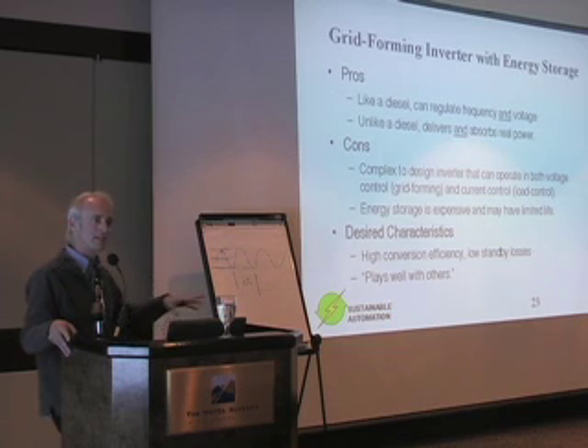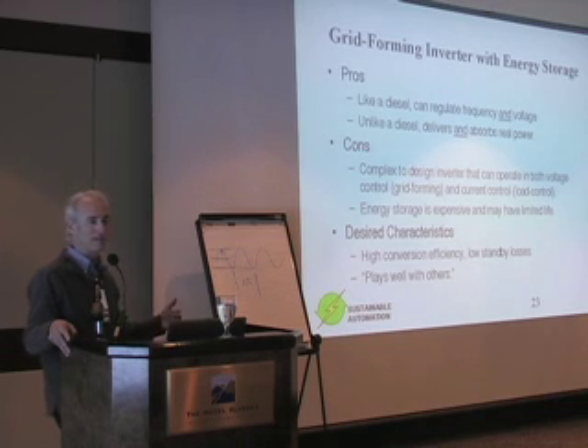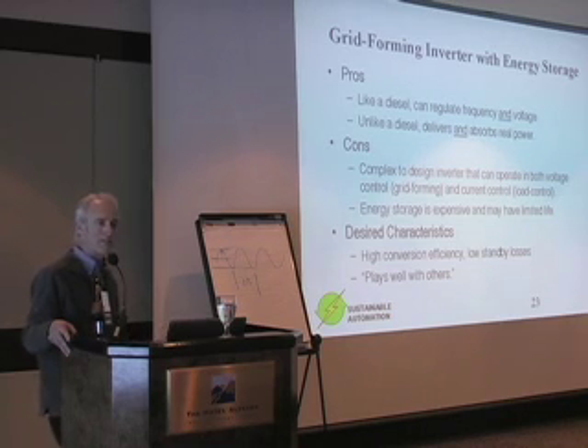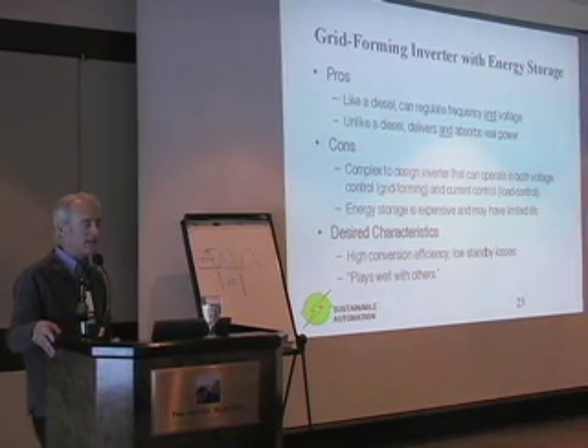The inverter only works to the extent that it has energy storage connected to it. At least that's the only way that it can provide or absorb real power, because that power has to go somewhere, and it comes from or is absorbed by the energy storage that's connected on the back end. That can be a battery bank, that can be a flywheel, and as Russell itemized this morning, there are many different types of storage and more coming on all the time. We're working on one project this year with a company that makes advanced lithium batteries, and they have some very, very exciting performance characteristics over traditional lead-acid batteries. But cost is the overriding issue pretty much in all forms of storage at this point.